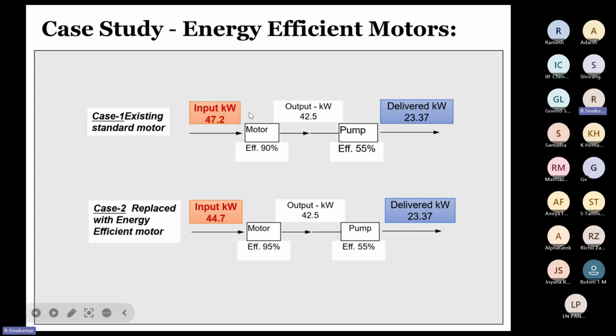So this is a case study. One motor is in a pump application. The existing motor delivers 42.5 kilowatt at the shaft with 90% motor efficiency, so the input is 47.2 kilowatt. The pump efficiency is only 55%, so the hydraulic power delivered at the pump output is 23.37 kilowatt. The same motor is replaced with a 95% efficiency one. Now you see, the motor output is the same, and the pump output, the hydraulic power, is also the same. But whereas the input was 47.2, it now consumes only 44.7, so nearly 2.5 units were saved here.